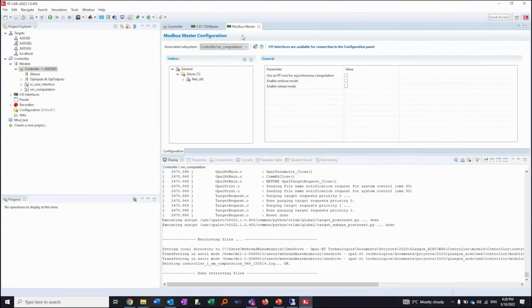The signals that it sends are the signals to close the breakers for switching on the capacitor bank in the network in case of an undervoltage. The model itself contains the wide area control algorithm that we have devised, which detects the undervoltage. If voltage drops below a certain threshold for a certain period of time, the logic will work as we have devised it and will send the signal back to close the breaker.